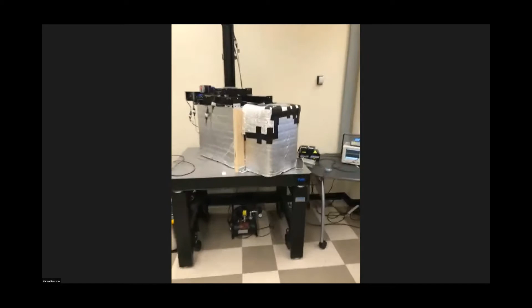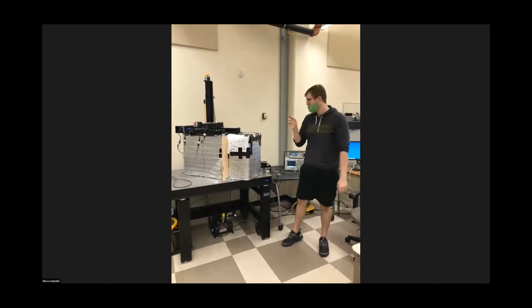Yeah, sure. So we have a hydrophone. Typically, it's in the box, today mounted on an XYZ gantry that has very, very fine precision. It's wrapped in 2 layers of thermal insulation to keep the temperature, at least at average room temperature, consistent within a degree Celsius. And it allows us to essentially characterize our different ultrasound transducers under different sets of parameters, which allows us to do different sets of stimulation and see the highest stimulation, the lowest stimulation we can use to elicit a response in human subjects. And it's all automated. Thank you, Jacob. And also we run simulations to understand what safety parameters we should be within when we do human experiments.